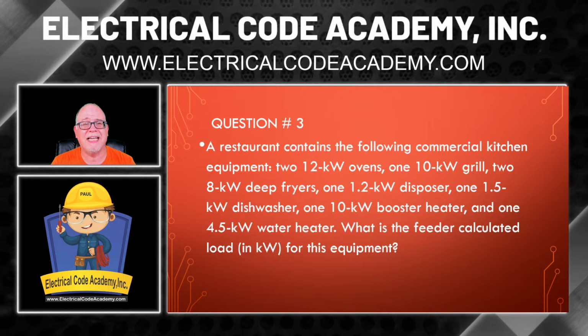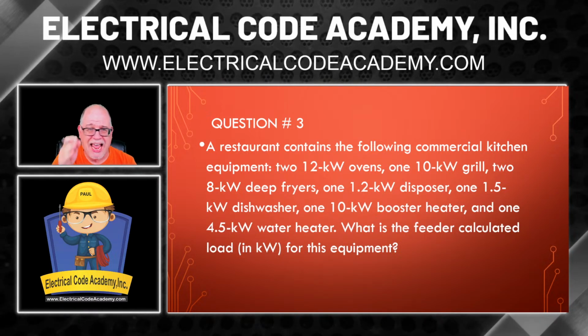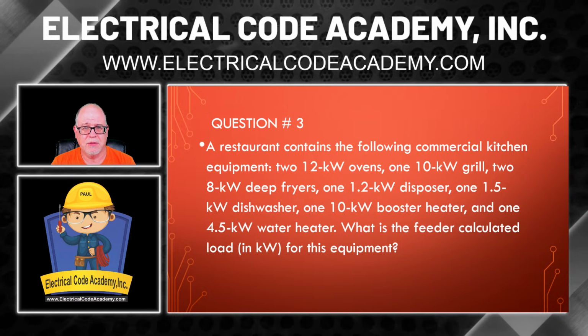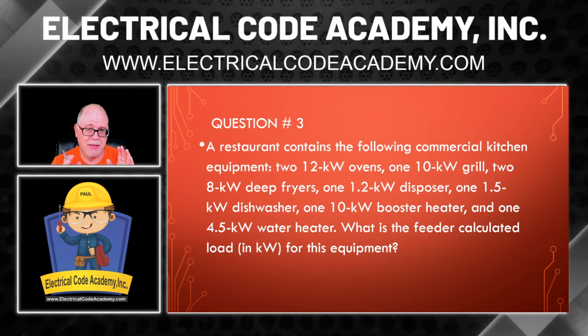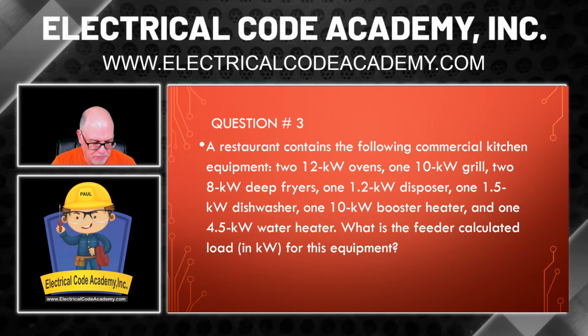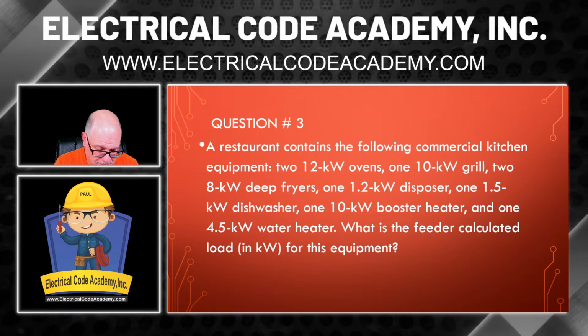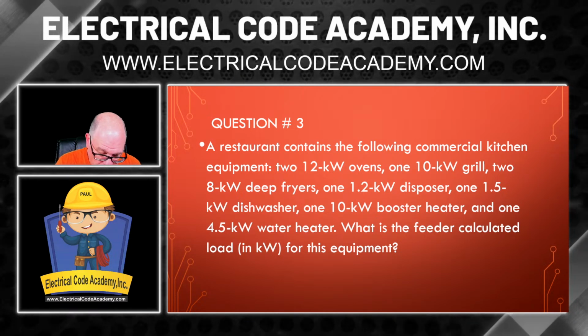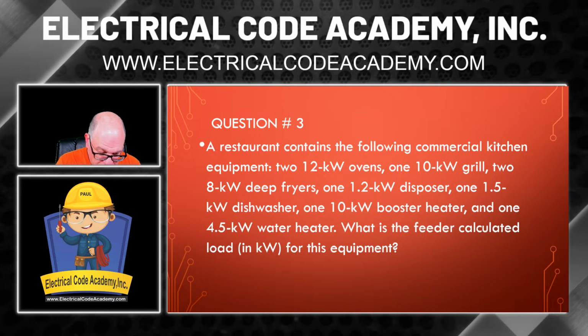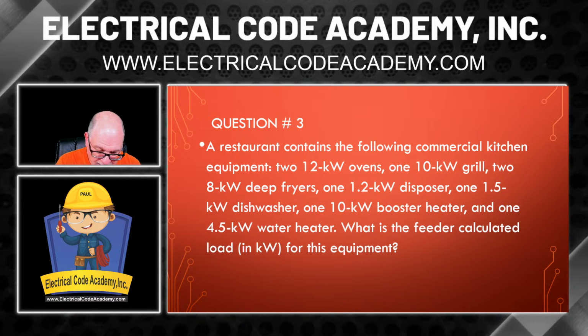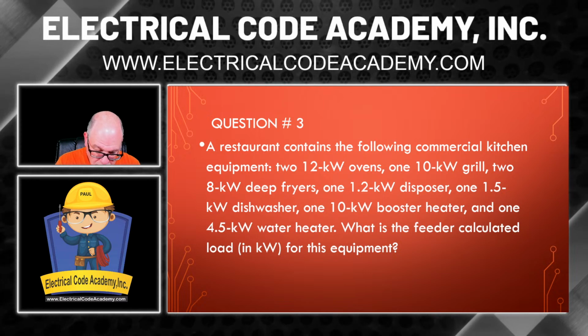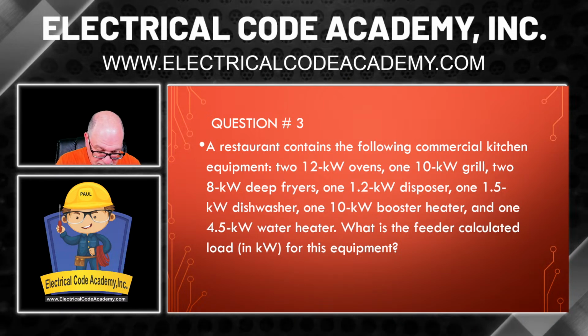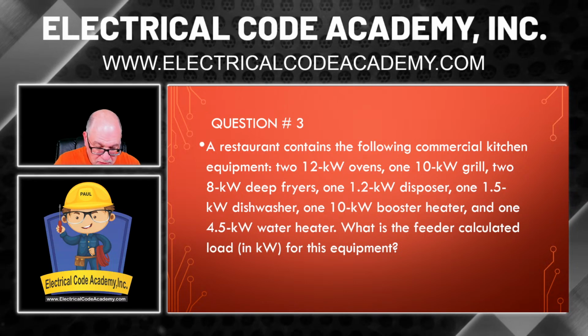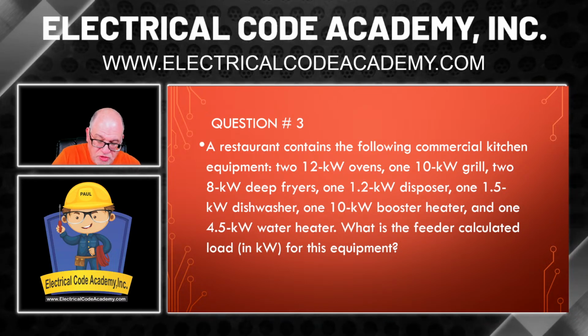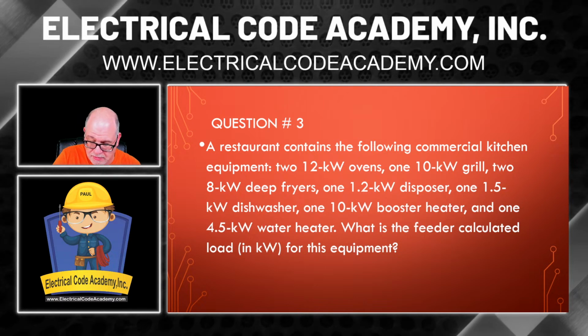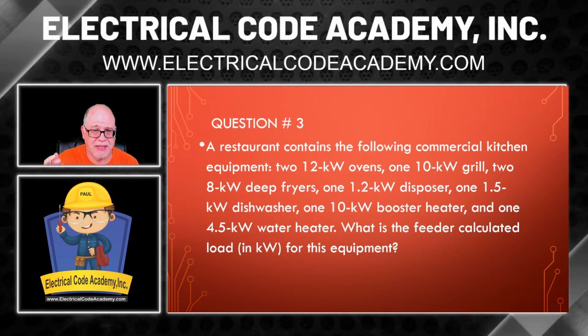I want to go on and get my total connected load. So I want to add everything up here, okay? Remember, you can pause this at any time, but I'm going to do that first before I even start looking at the code, all right? So I'm going to add up 12 plus 12 plus 10 plus 8 plus 8 plus 1.2 plus 1.5 plus 10 plus 4.5. That gave me 67.2 kW, okay? So at least I know what they're all added up to be, right?